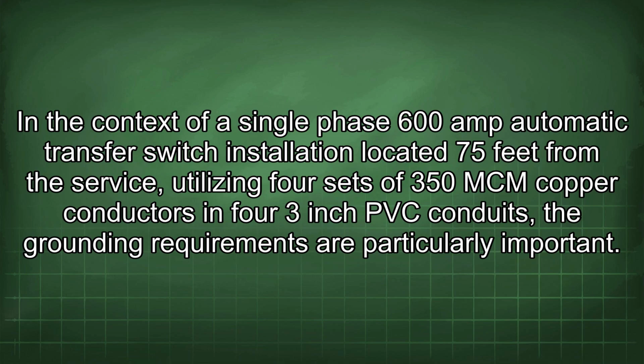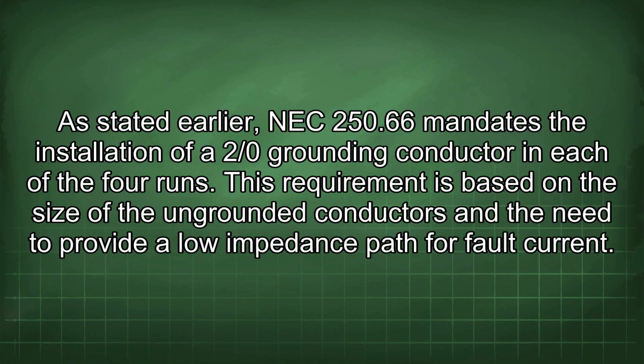In the context of a single-phase 600 amp automatic transfer switch installation located 75 feet from the service, utilizing 4 sets of 350 mcm copper conductors and 4 3-inch PVC conduits, the grounding requirements are particularly important. As stated earlier, NEC 250.66 mandates the installation of a 2/0 grounding conductor in each of the 4 runs.